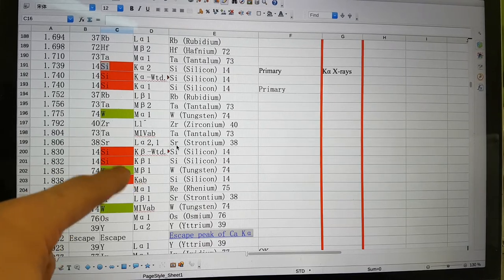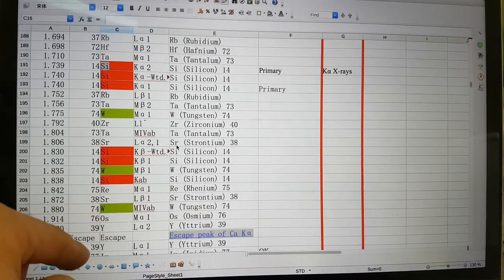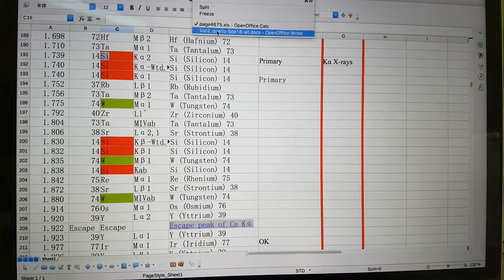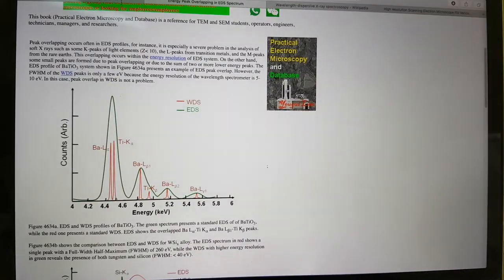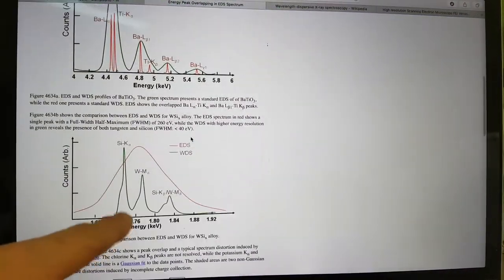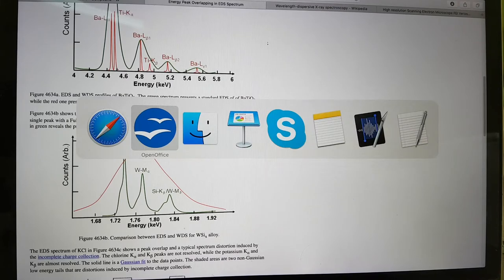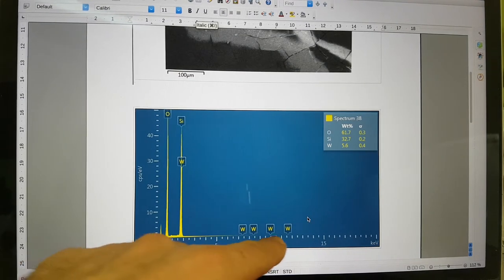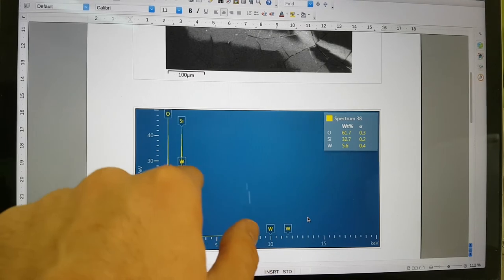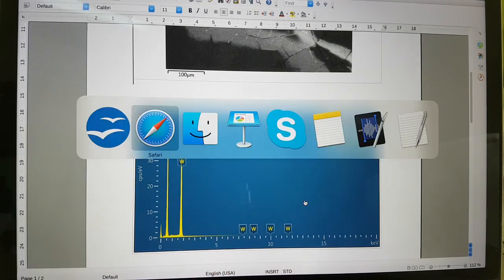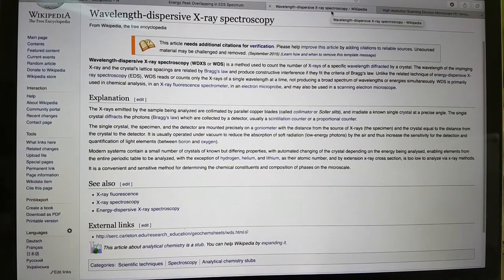And the tungsten is right in the middle here with this particular x-ray coming back. So this is where the confusion is coming when we look at this maybe confusion band here, which is also talked about in this energy overlap here. So there's a couple of ways we can look for problems and fix them. And one is to look for higher energy peaks and see if they are there in something that's determined at a lower level. Or to potentially use the wavelength dispersive x-ray spectroscopy.